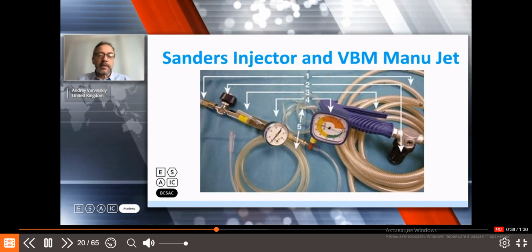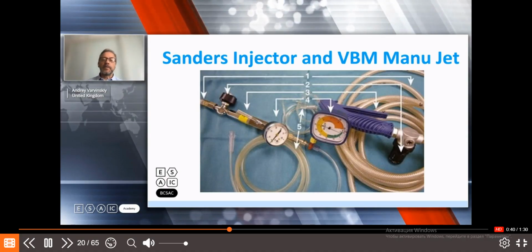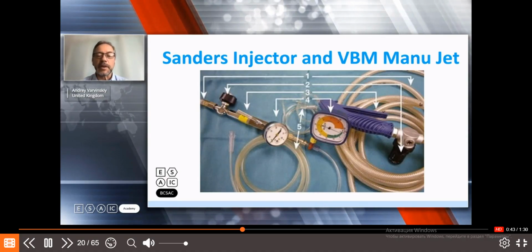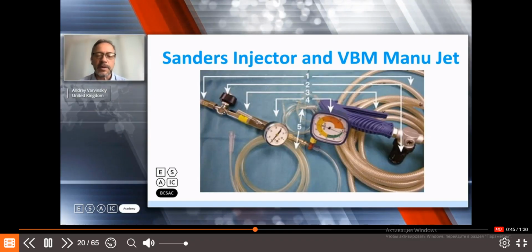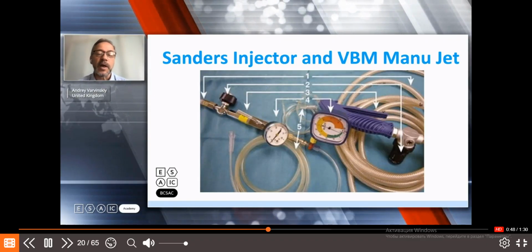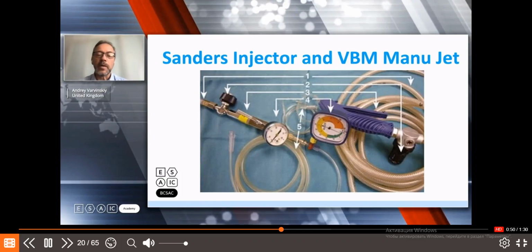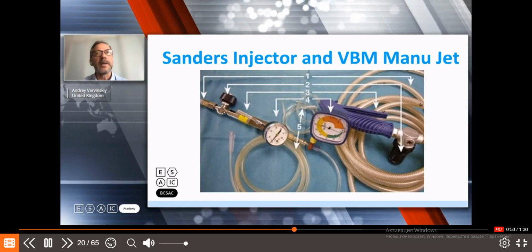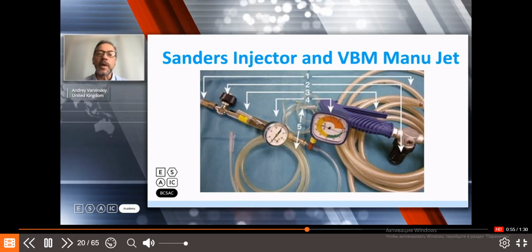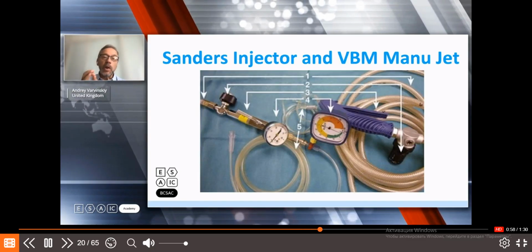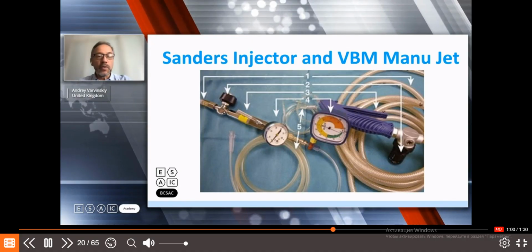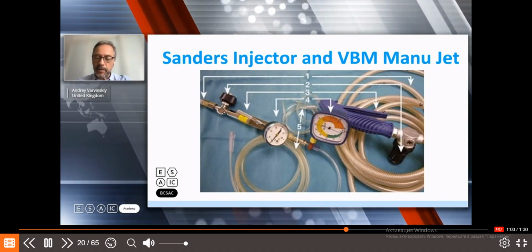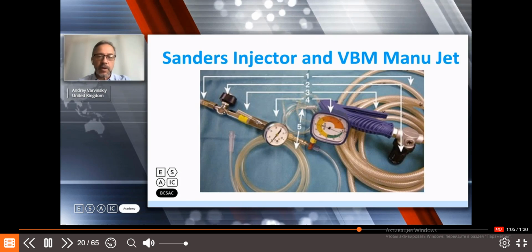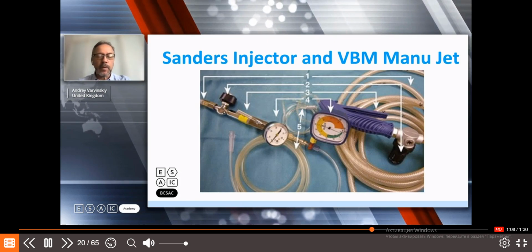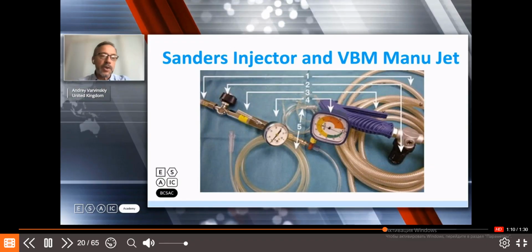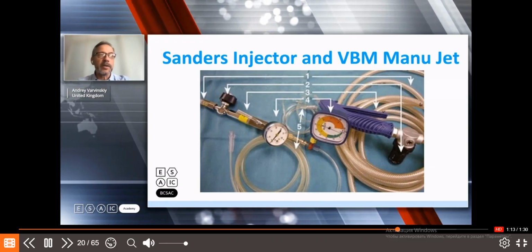With the Manujet, the only advance from the Sanders injector is that it gives you guidance on the screen of where to put your pressure depending on the age and the weight of your patient, and also you can lock that pressure so you do not accidentally exceed it and produce a pneumothorax. But it's a very crude device, and obviously can only inject air under pressure into the patient's airway.